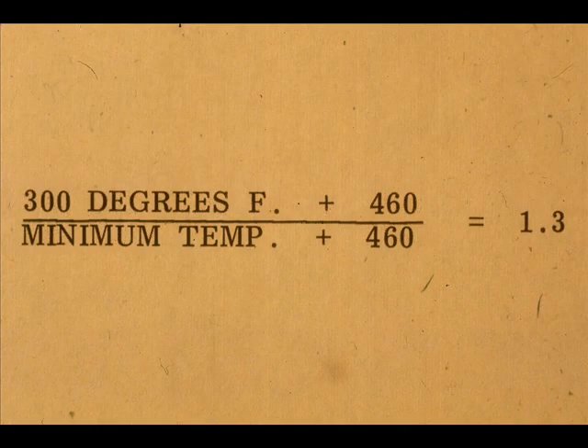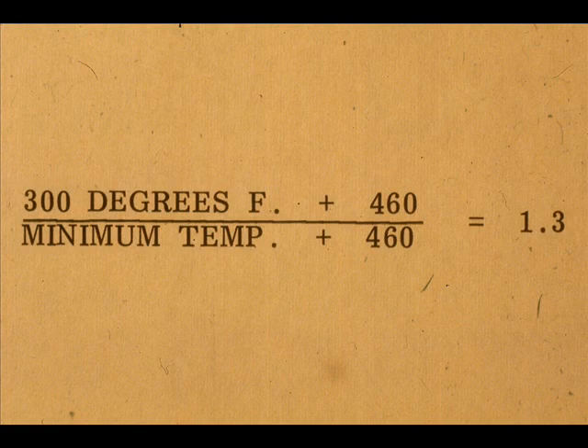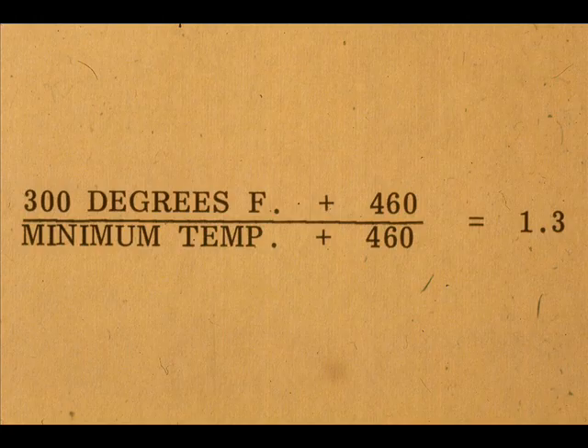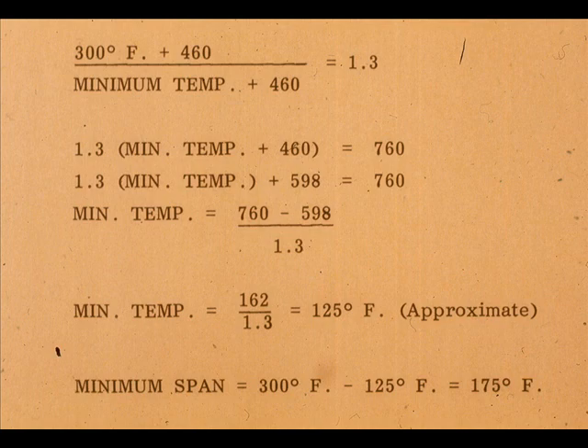For example, if we wanted the maximum temperature of the span to be 300 degrees Fahrenheit, the minimum temperature would have to be 125 degrees Fahrenheit or lower. Our span could not be any less than 175 degrees.